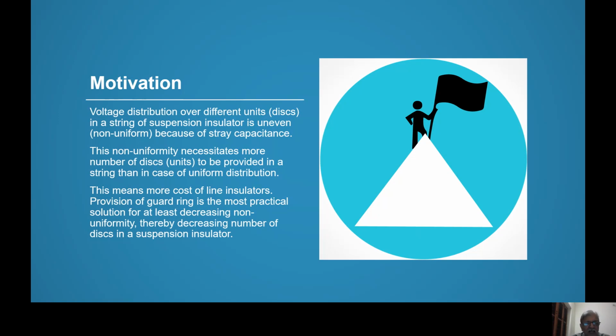No doubt, it is not so that people have not tried to make this capacitance uniform. Line stray capacitance will be there, you can't avoid it. But yet, with the presence of that, the capacitance across each disk can be made more or less even by different techniques. So one of the techniques is grading the ring, grading the disk. That means don't use the same capacitance for the disk.